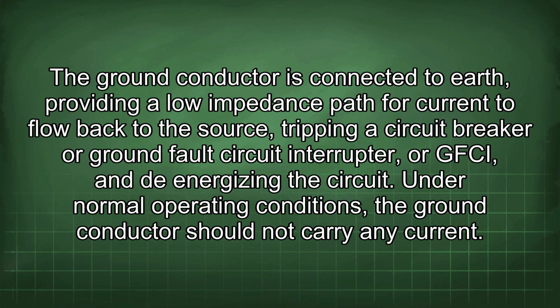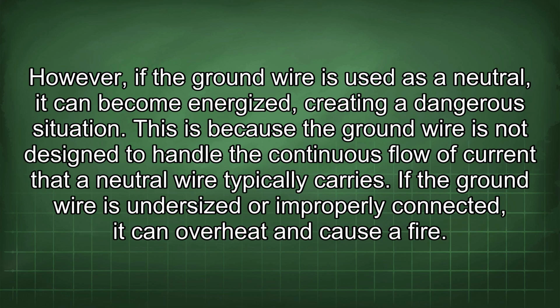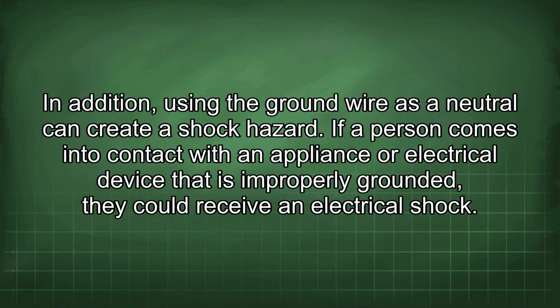Under normal operating conditions, the ground conductor should not carry any current. However, if the ground wire is used as a neutral, it can become energized, creating a dangerous situation. This is because the ground wire is not designed to handle the continuous flow of current that a neutral wire typically carries. If the ground wire is undersized or improperly connected, it can overheat and cause a fire. In addition, using the ground wire as a neutral can create a shock hazard.